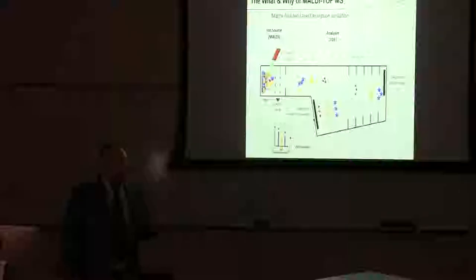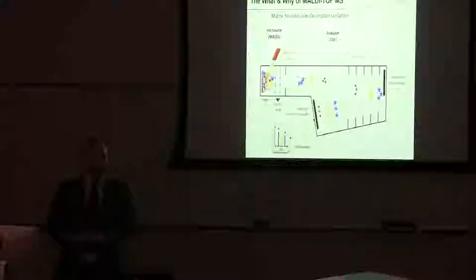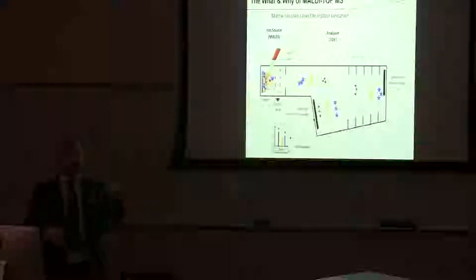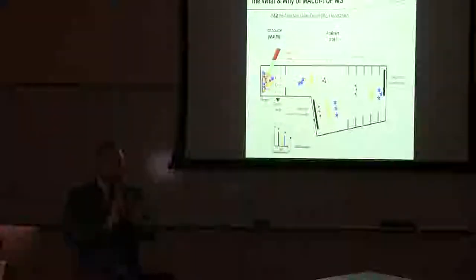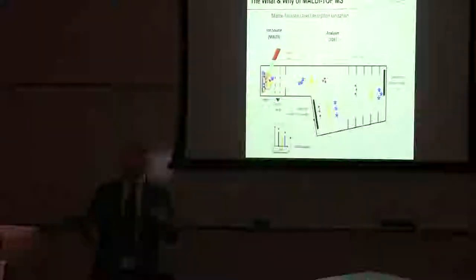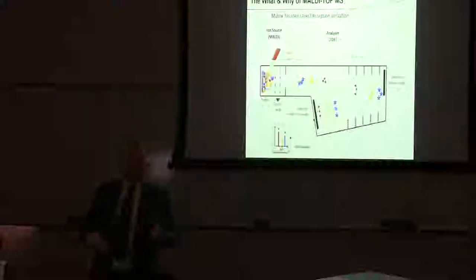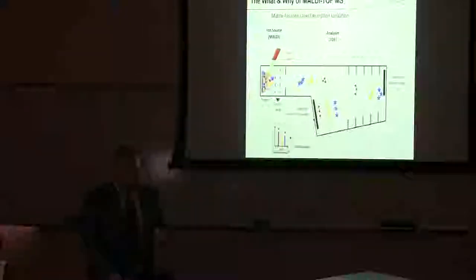In the example of the MALDI-TOF and linear mode instrumentation, you have a direct path from the ion source to the detector. This is very beneficial for measuring very high molecular weight species. But for lower molecular weight species, you can then send them through a reflectron to help focus some of the dispersion of the ions so that you get very high resolution. So we would typically look at mass range, say, 1 to 5,000 to get that isotopic resolution and accurate mass using reflectron mode. You can still look at higher molecular weight species in reflectron, but you would typically be then still using average molecular weight.